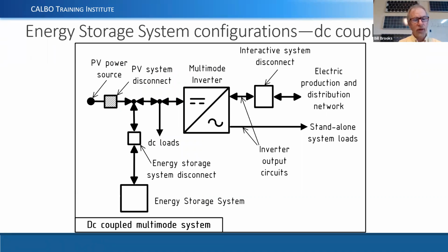Okay, some of the energy storage configurations we have out there, we call these DC coupled or DC interconnected systems, where we'll be bringing the PV array and the energy storage together on the DC side of the multi-mode inverter. There are quite a few of these products out there, including Generac, which is certainly a common one, and there are others. So this would be a DC connected energy storage system and a DC connected PV system. And the PV system actually has a DC disconnect for the PV system disconnect.